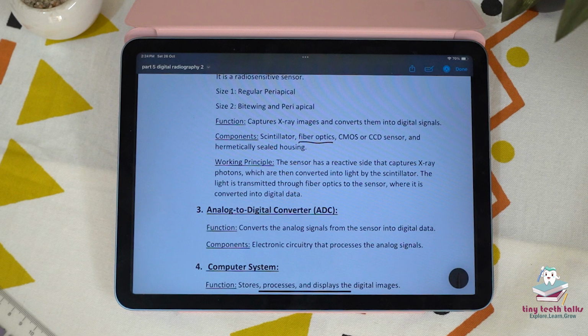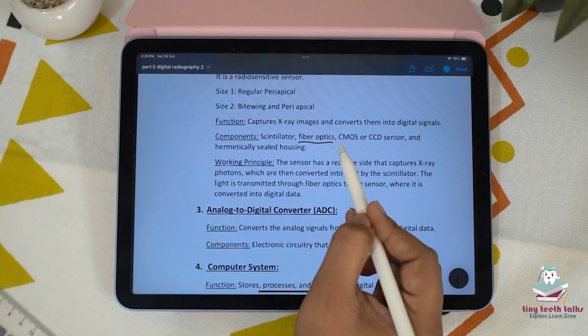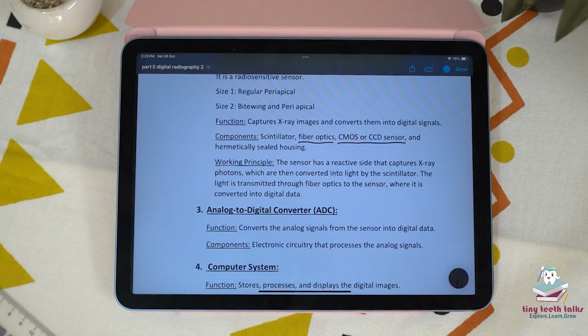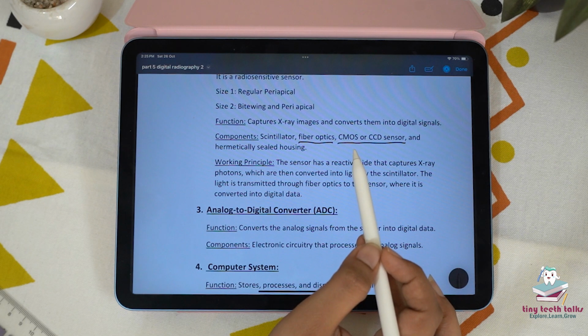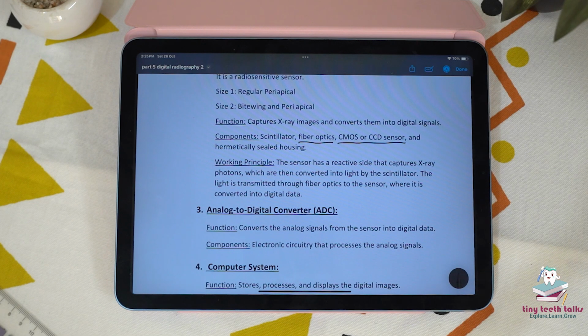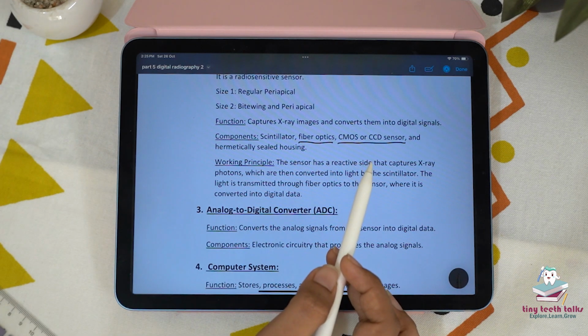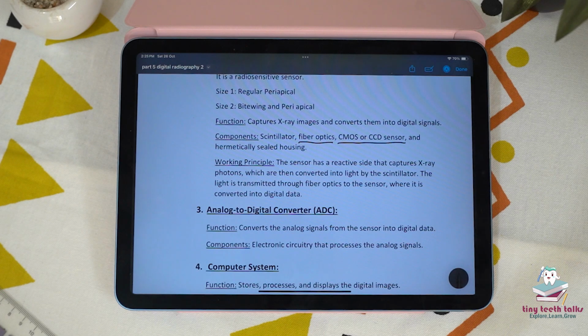These fiber optics transmit the light from the scintillator to the sensors. It ensures that the light signal is efficiently and accurately transferred to the sensor without significant loss or distortion. The optical fiber guides the light photons from the scintillator directly to the sensor, maintaining the integrity of the image. Then CMOS and CCD sensors convert the light photons into an electronic signal. Complementary metal oxide semiconductor is known for lower power consumption and faster readout times. Then charge coupled device is known for higher image quality and sensitivity.